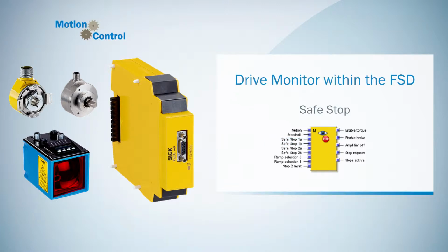For triggering the function Safe Stop 2, there are the input saveStop2A as well as the optional input saveStop2B. These inputs are also normally high and trigger the Safe Stop 2 if one of them goes low. At a Safe Stop 2, the brake operation starts via an emergency stop declaration. This brake operation will be monitored by the drive monitoring device. When the speed is below the configured standstill limit, then the function Safe Operating Stop will be used to remain the drive in the position where the function was activated.